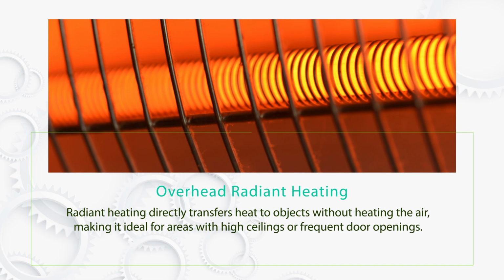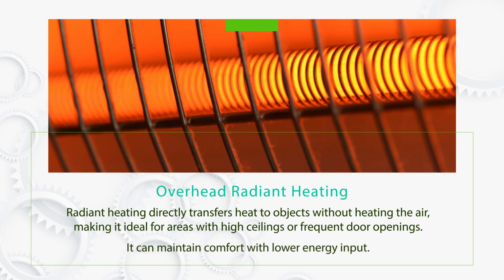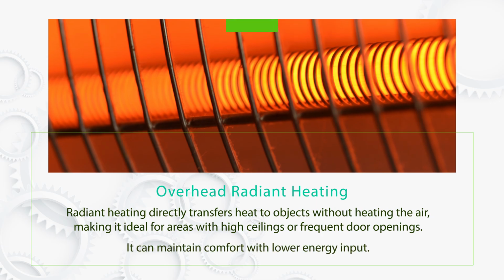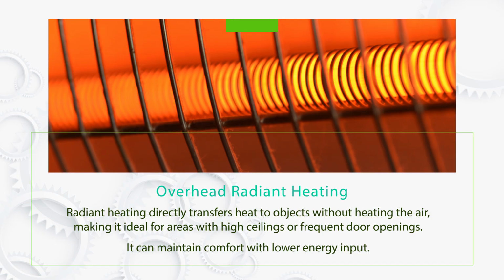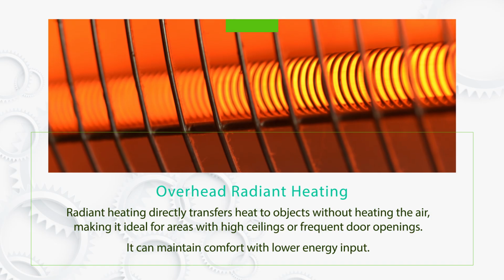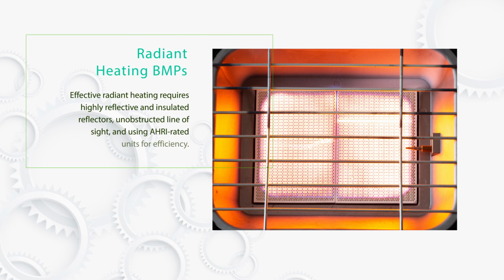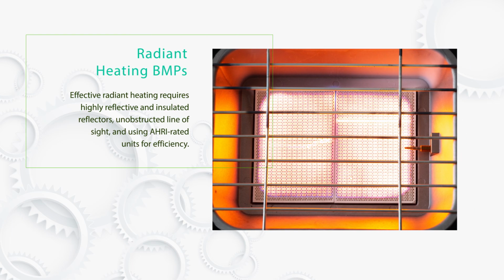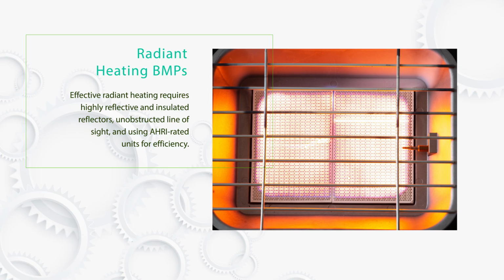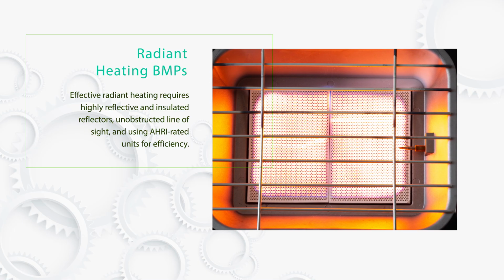Radiant heating directly transfers heat to objects without heating the air, making it ideal for areas with high ceilings or frequent door openings. It can maintain comfort with lower energy input. Effective radiant heating requires highly reflective and insulated reflectors, unobstructed line of sight, and using AHRI-rated units for efficiency.